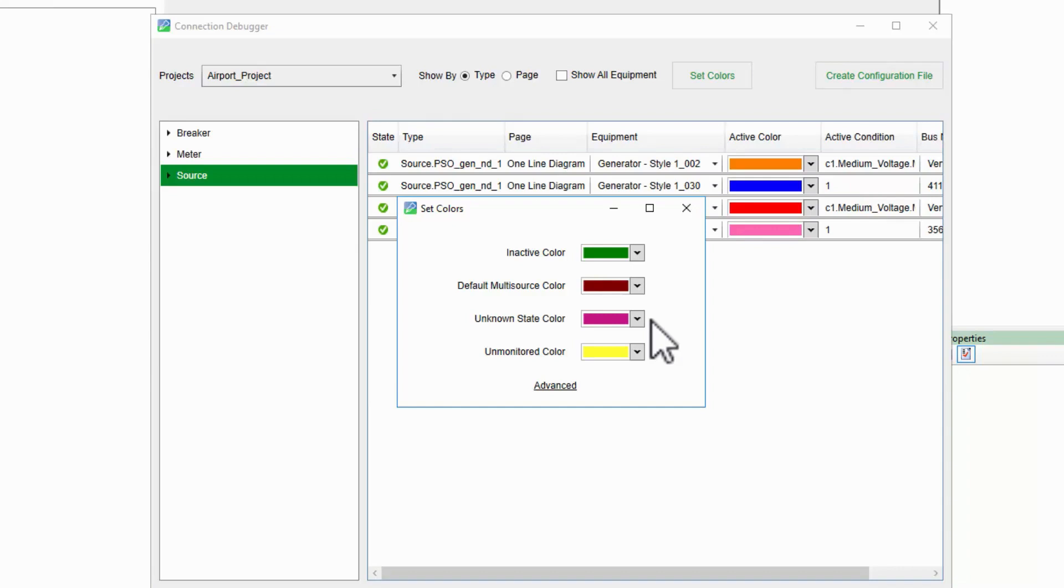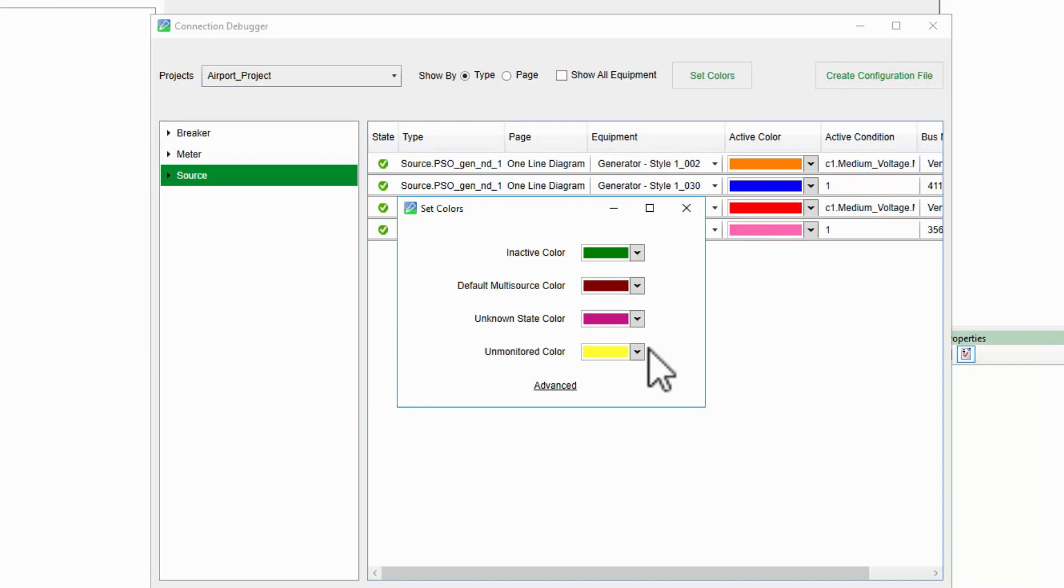Finally, if a bus would otherwise be de-energized, say the sources are off or the breakers are open, but a connected meter component is still active, we'll see the unmonitored color. This is to tell us that the bus is energized, but we aren't sure which source is energizing it.